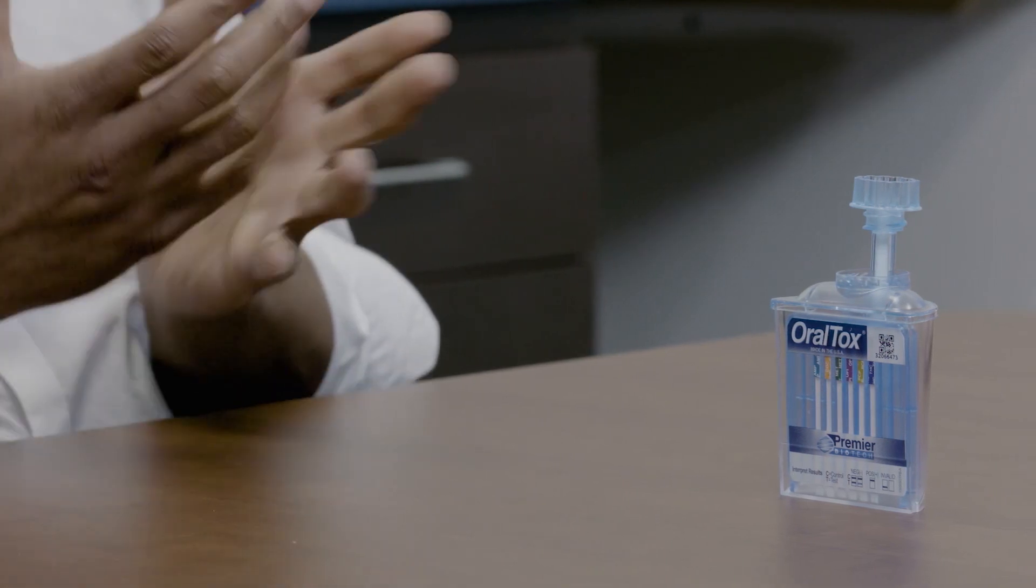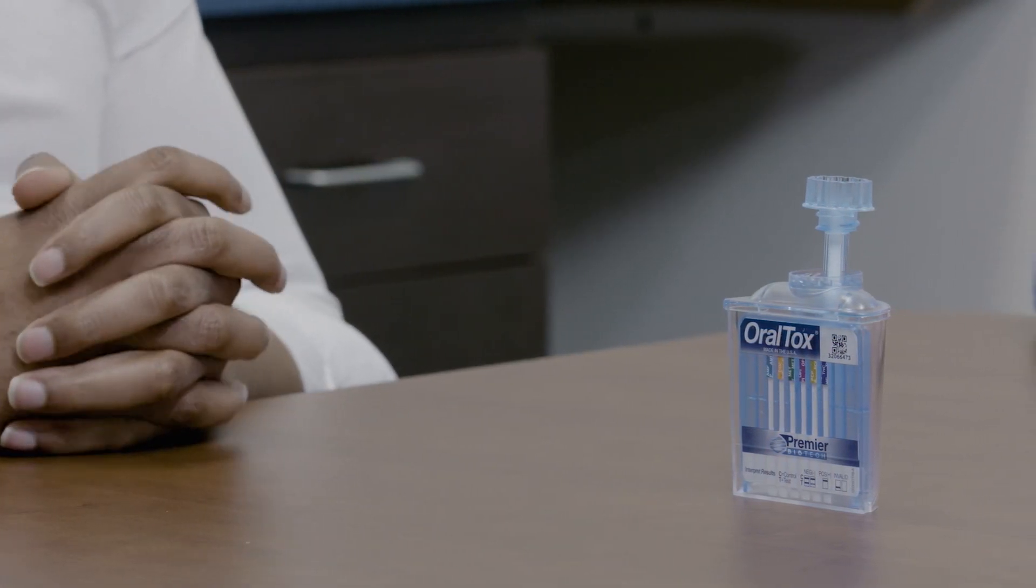This action should break the bubbles and allow the test to run as intended. Follow your organization's established protocol for presumptive positive results. After the results have been interpreted, the OralTox device may be thrown in a regular trash receptacle. Results should not be read after 20 minutes.